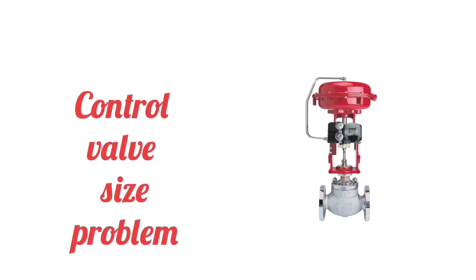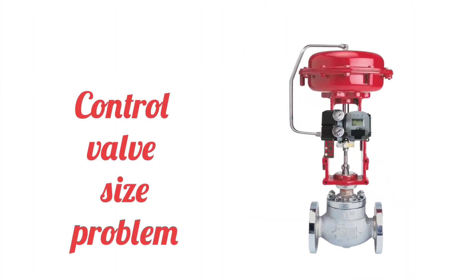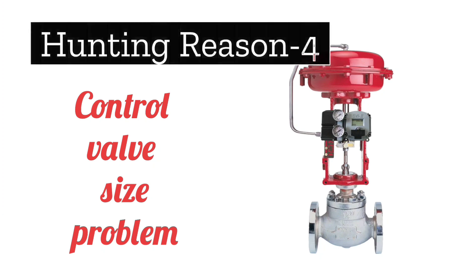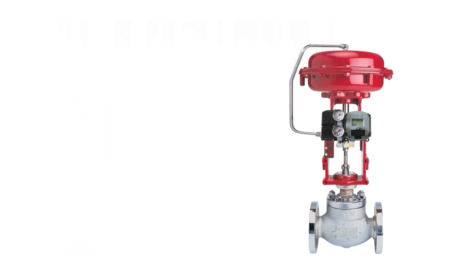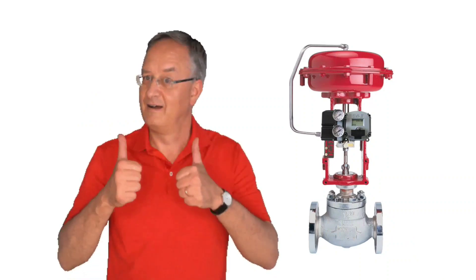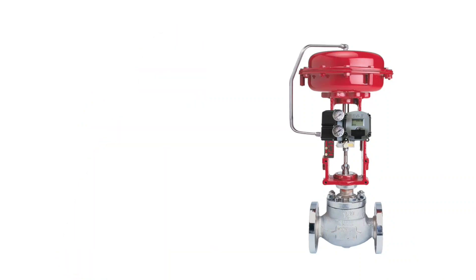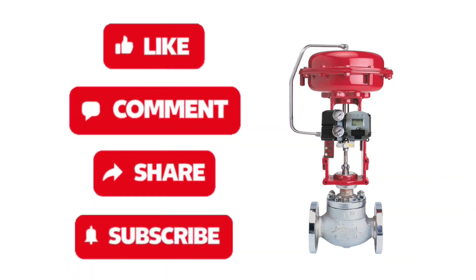The control valve you are using — even if it is not of proper size — this may also be a cause of the hunting problem in control valves. So these were some reasons due to which control valve hunting problem occurs.